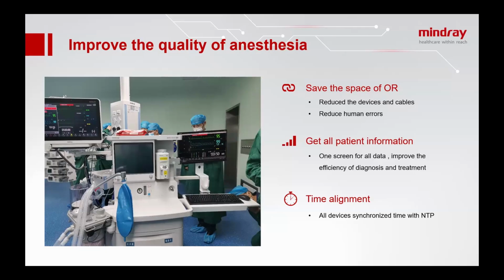Why time alignment or synchronized time on all devices is crucial is for the induction and for the status of the patient. Whenever there's an induction on infusion set, on a docking system, or the amount concentrated delivered from the vaporizers on an anesthesia machine, the time sync allows for accurate record keeping on the patient monitor for the reaction of these drugs induced.